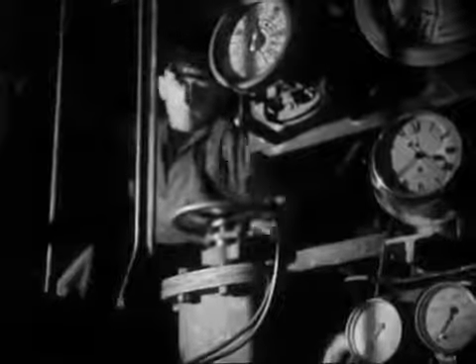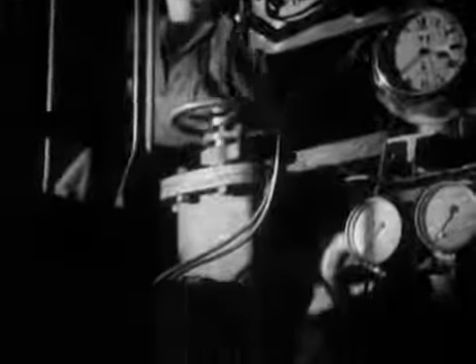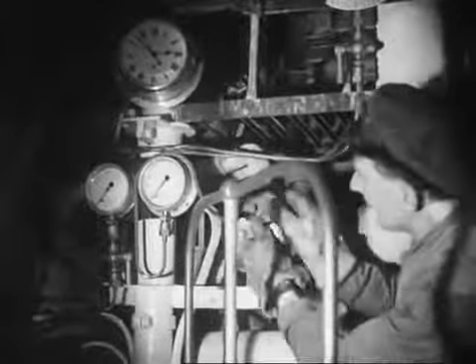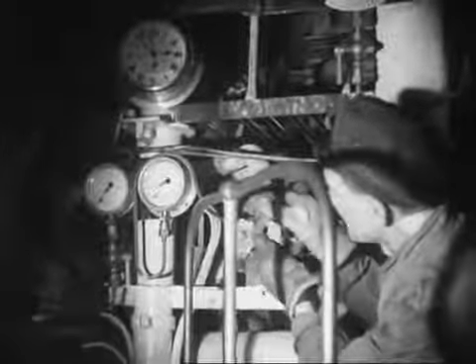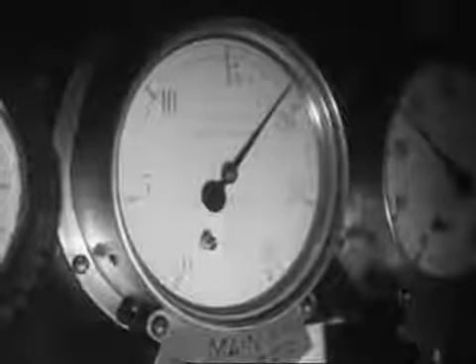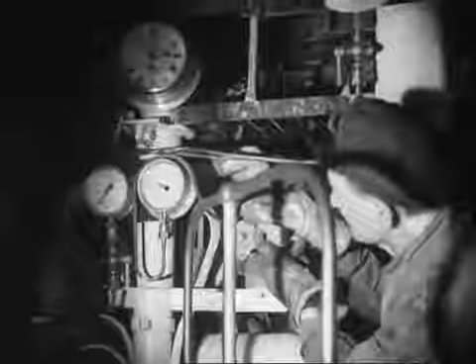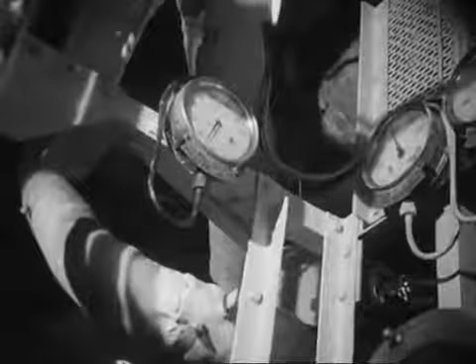Well, things are now nearly ready. Valves on the closed feed system up to the main feed pump are opened, also the air ejector. The vacuum is worked up to 20 inches using a minimum of steam, for the lower the pressure at the exhaust end of the turbine, the greater the efficiency, because the work done by a given quantity of steam depends upon the difference of initial and final pressures, that is, boiler pressure and condenser vacuum.